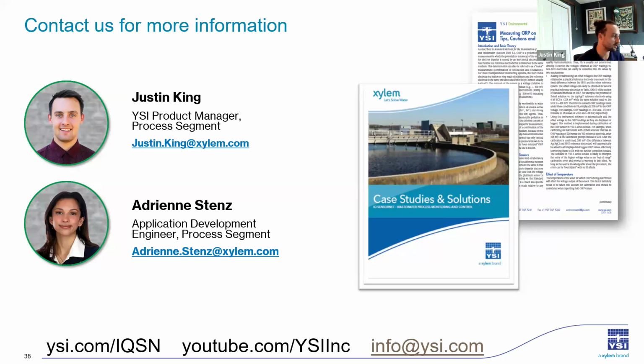I should mention too that we do offer a variety of different air cleaning options as well. We've got 3 different air blast cleaning systems where we take compressed air and blow it over the sensor face at different time intervals. We've got a medium, a high, and a low level PSI cleaning option that allow us to clean the sensors while they're in situ, while they're in the process. And that helps elongate the lifetime of the sensor, as well as the period of time in which an operator would need to pull and do any sort of manual maintenance on the sensor.